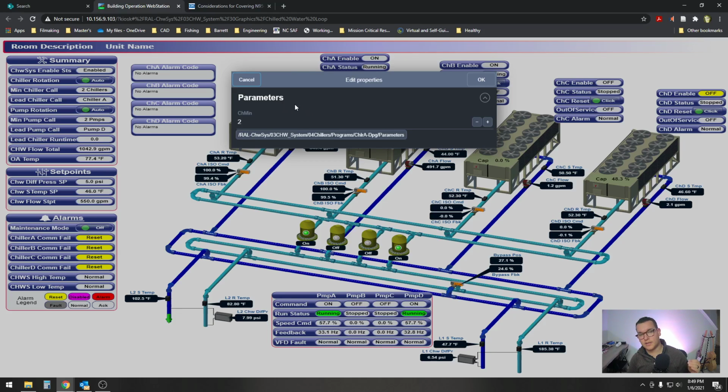So we tell the system, hey, you have to run 2 units to maintain redundancy, because that's just what we do. We run 2 units just in case one fails, the other one doesn't. It takes a long time for them to stage up and run. Therefore, we need to have 2. That way, it just takes the load and is a lot faster, and our temps don't get crazy.